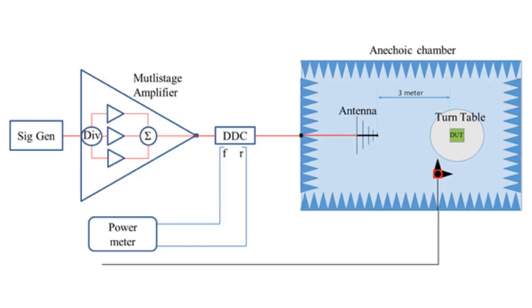At each step, the frequency is held, the level adjusted to the required field strength V/m as measured by a field sensor, a prescribed modulation mode is initiated, and then the conditions held for a dwell time. The EUT should be monitored to detect faulty operation during the test.